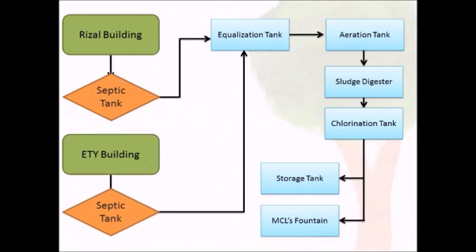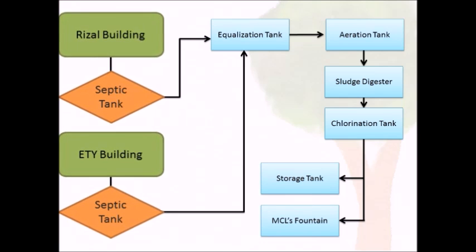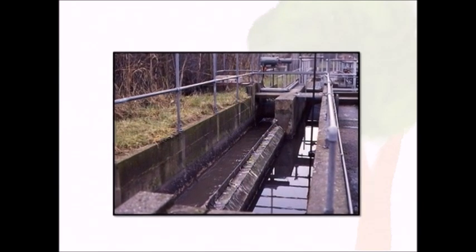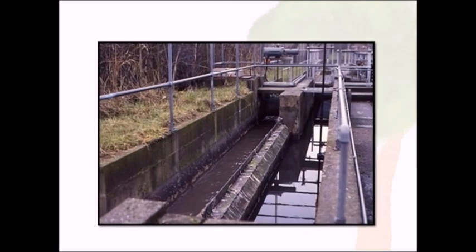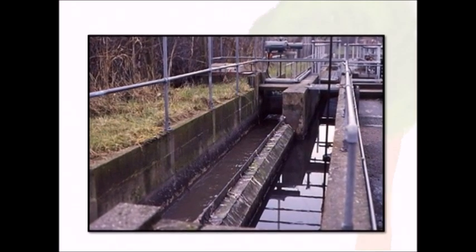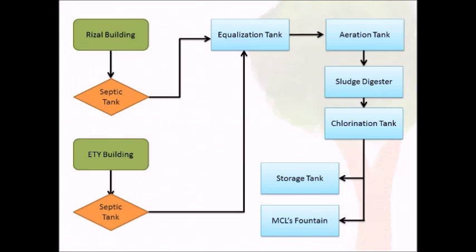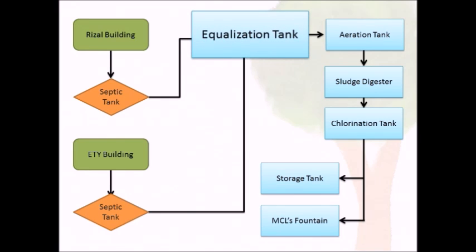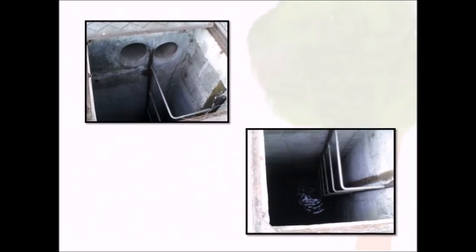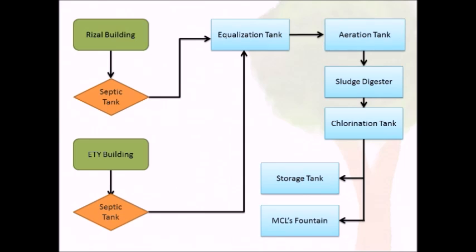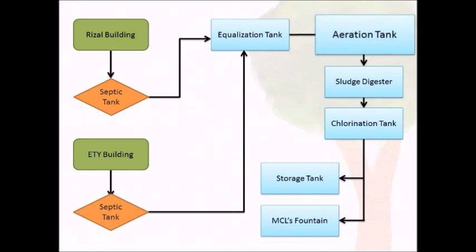The wastewater coming from the septic tank from the JPE Riesel building and ETY building will pass through the inlet channel. The inlet channel holds raw wastewater. The wastewater flows through a grease trap. Next is the equalization tank, which serves to receive all the influent from those two pipelines, and is subjected to pre-aeration and odor removal before transferring the volume to the aeration tank.